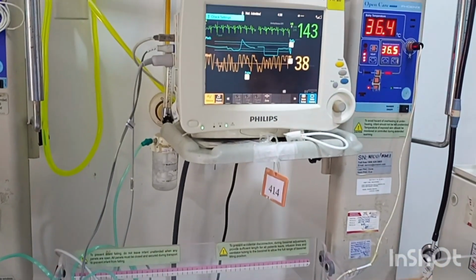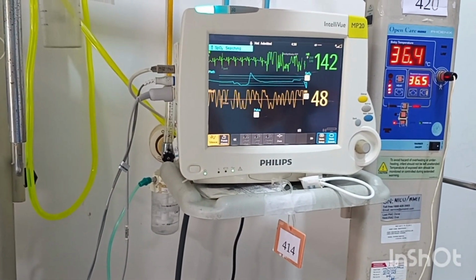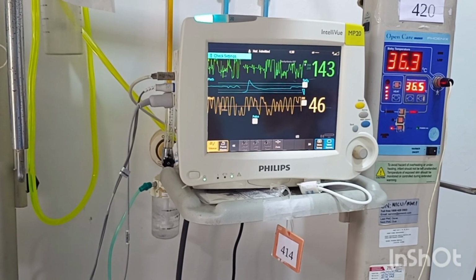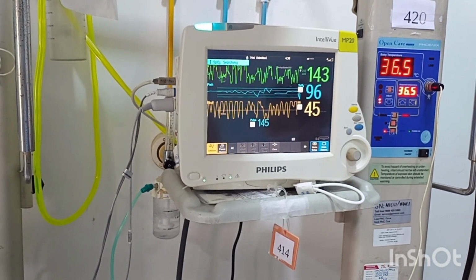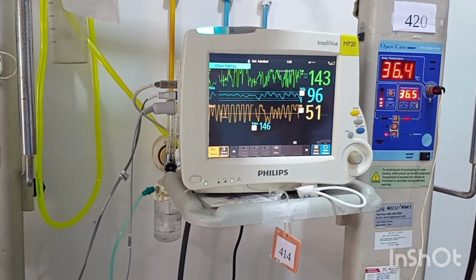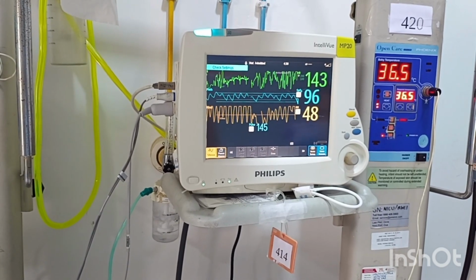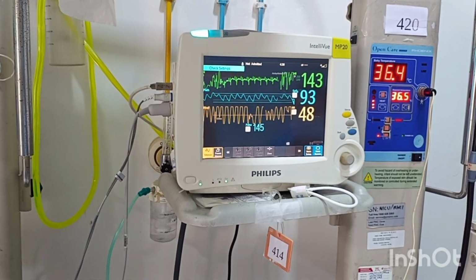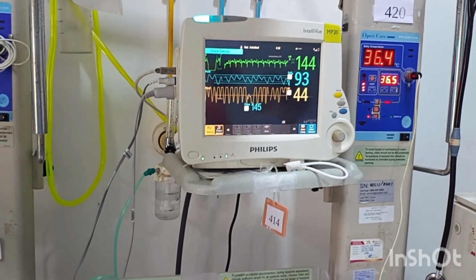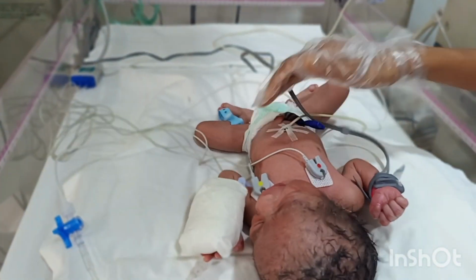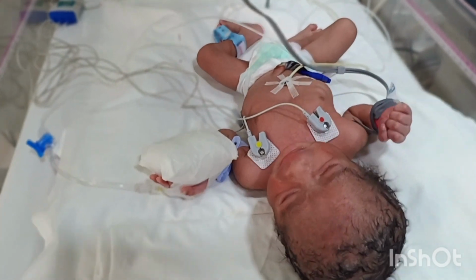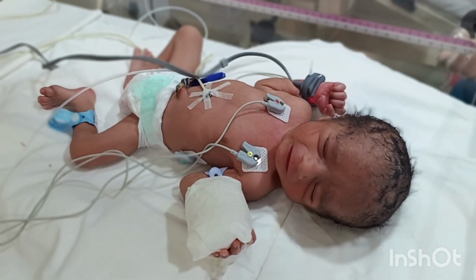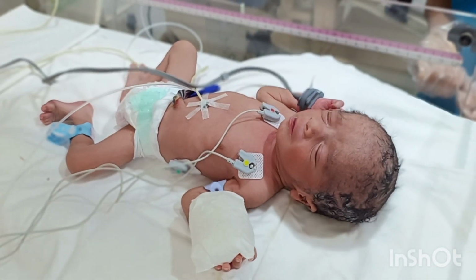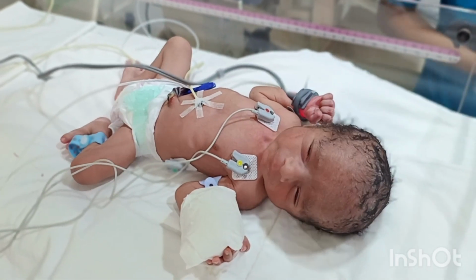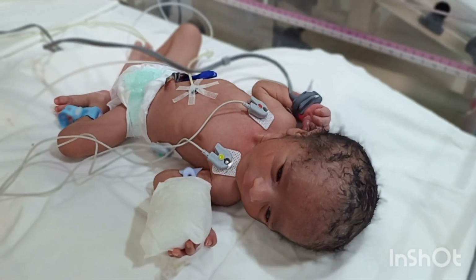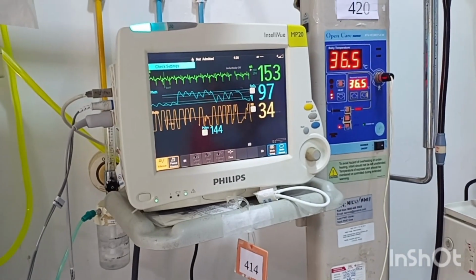The baby's skin is not getting any injury from the probe. So you can see that the machine has started showing the readings, but we have to take care that the graphs are symmetrical before taking the reading. If the baby moves or cries, the graphs are not coming properly, and we should not trust the reading. We have to calm the baby and then only see whether the graphs of the machine are coming properly, and then only we can take the reading. Here the baby is calm now, and we can see the graphs are also coming down.